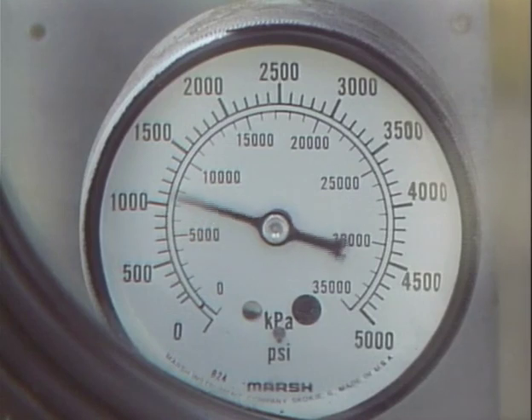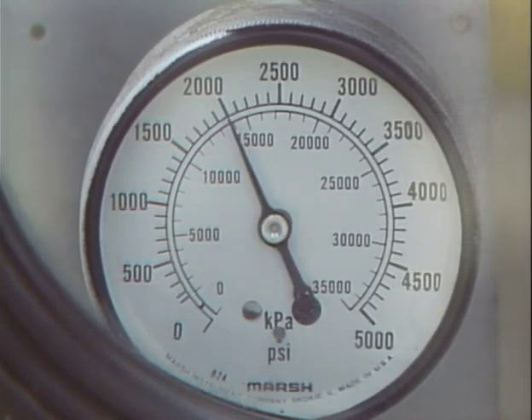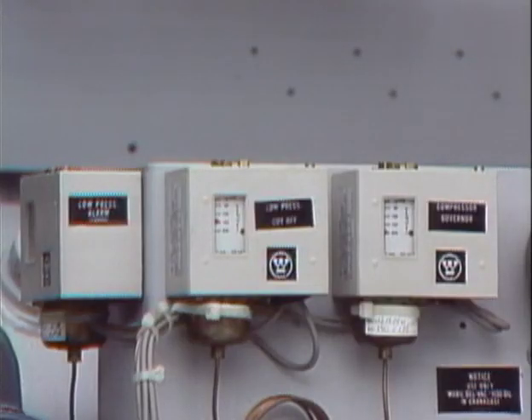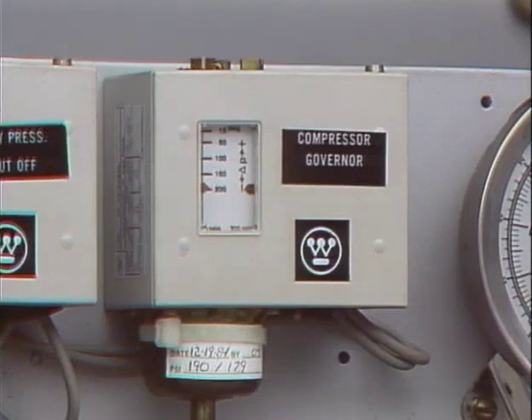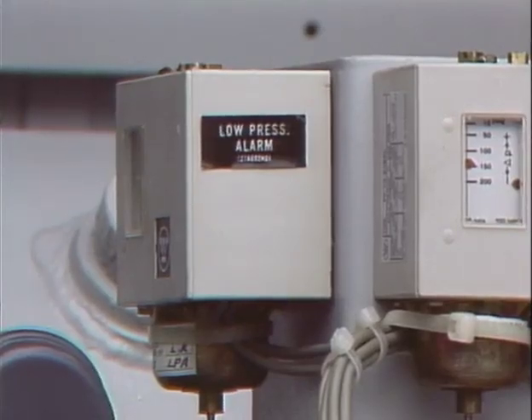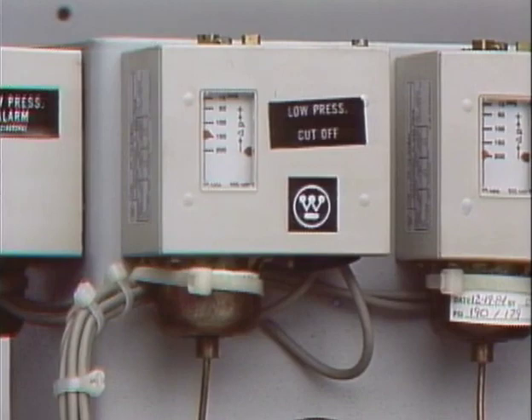For a hydraulic operating mechanism, the hydraulic fluid system pressure is checked, and the hydraulic fluid level is checked. Then, for both pneumatic and hydraulic operating mechanisms, the operation of various pressure switches is checked. Pressure switches typically include a compressor governor switch, a low-pressure alarm switch, and a low-pressure cutoff switch.